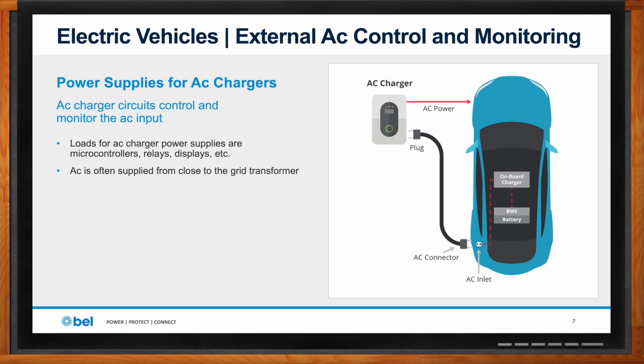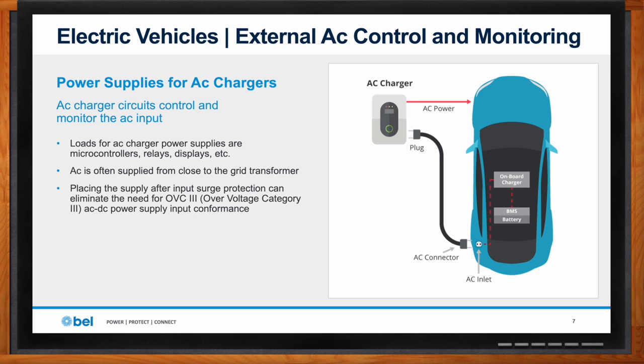When devices are hardwired into the grid, they tend to see more extreme voltage transients, because transients come down the grid. Therefore there's what's known as overvoltage categories for transient suppression. When hardwired into the grid, you move into OVC level 3 for power supply input protection. So either you purchase AC-DC power supplies with OVC level 3 protection designed in, or you use external components to build an OVC level 3 filter. Either approach can be done for AC-DC power supplies.